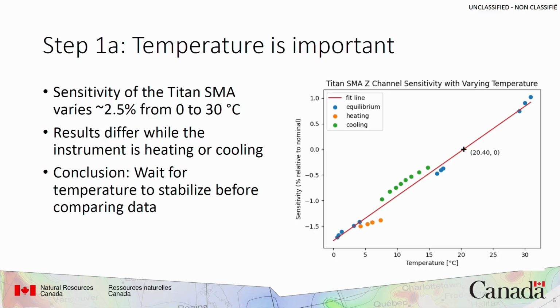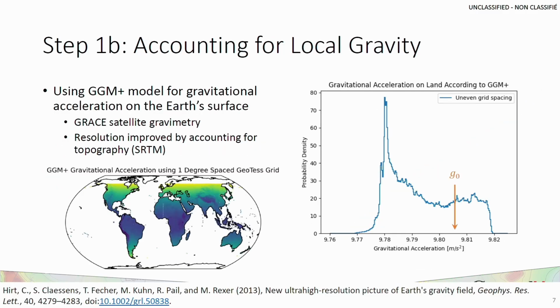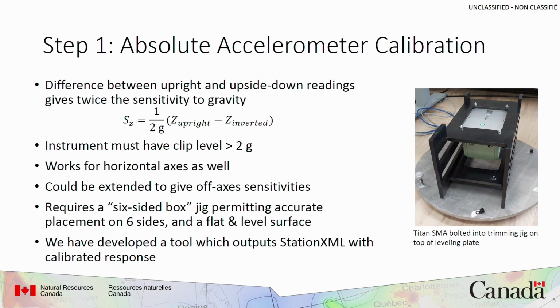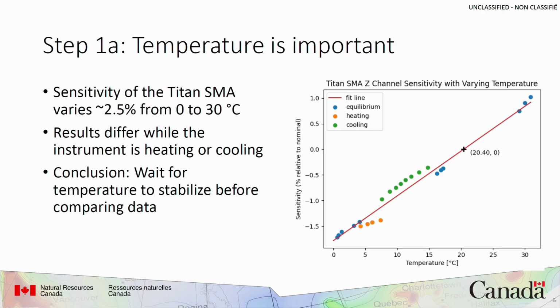Absolute accelerometer calibration works by taking readings right side up and upside down and taking the difference. The main requirement is a 6-sided box jig, which facilitates accurate placement. It's shown in the picture on the right in an upside down position. The even trickier position is the one where the cables are pointing down and you have to stand it upright without interfering with those cables. The instrument has to have a clip level of at least 2 Gs, and we place the sensor on all 6 sides to get 3 sensitivities. The picture shows a leveling plate, which is not required if you have a flat, level surface. And the whole process takes a few seconds per side and a minute total.